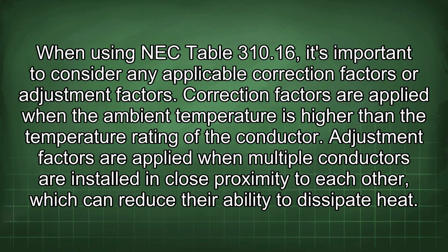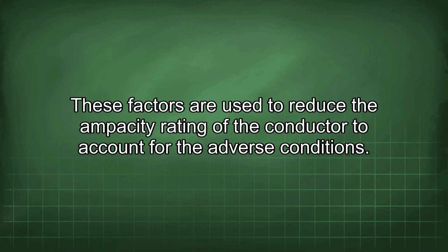When using NEC Table 310.16, it's important to consider any applicable correction factors or adjustment factors. Correction factors are applied when the ambient temperature is higher than the temperature rating of the conductor. Adjustment factors are applied when multiple conductors are installed in close proximity to each other, which can reduce their ability to dissipate heat. These factors are used to reduce the ampacity rating of the conductor to account for the adverse conditions.